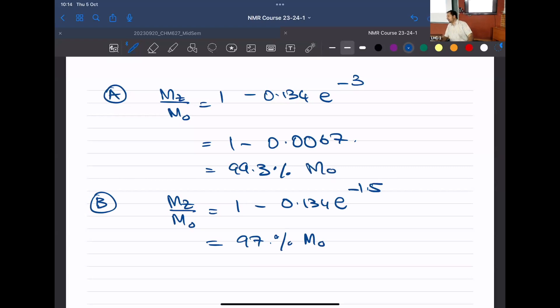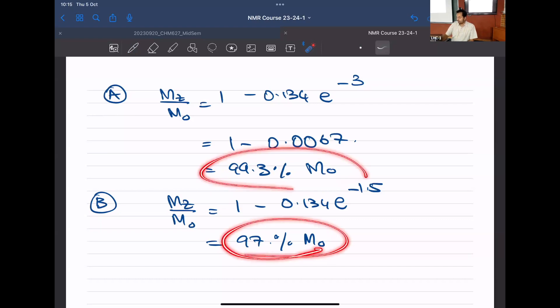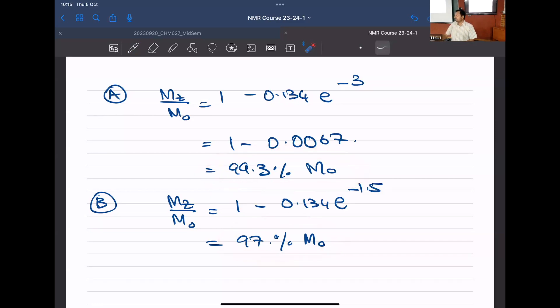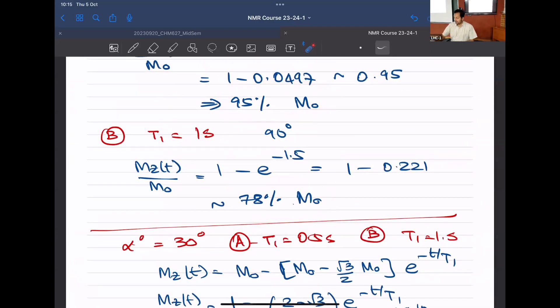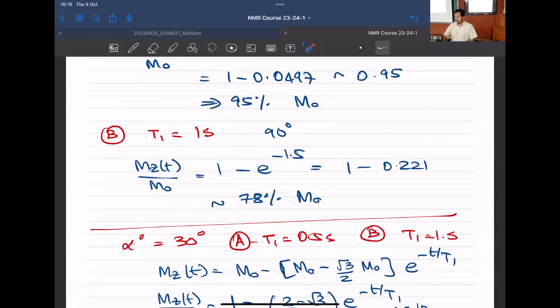Irrespective of T1 value, the 30-degree pulse allows magnetization to recover very close to thermal equilibrium. This emphasizes that running an experiment at a lower flip angle gives recovery close to equilibrium across spins with different T1 values, for a reasonably set D1 + AQ. With 90-degree pulses we had a ~20% disparity between two spins in the same sample — if you integrate, there will be a 20% error.